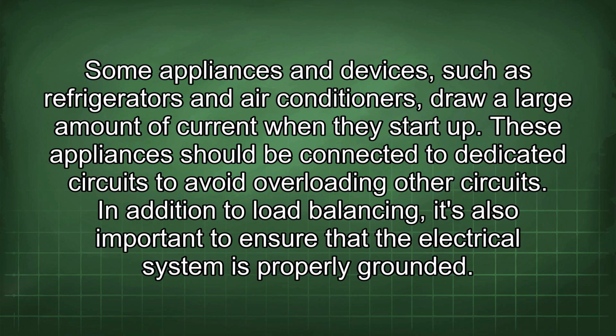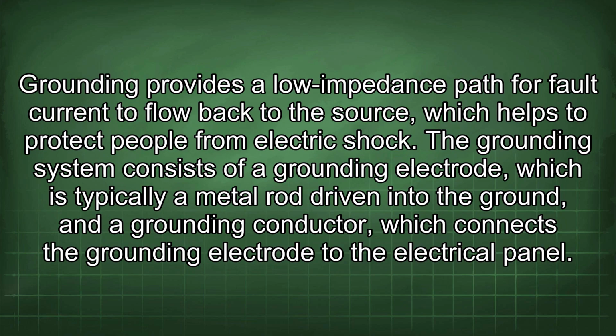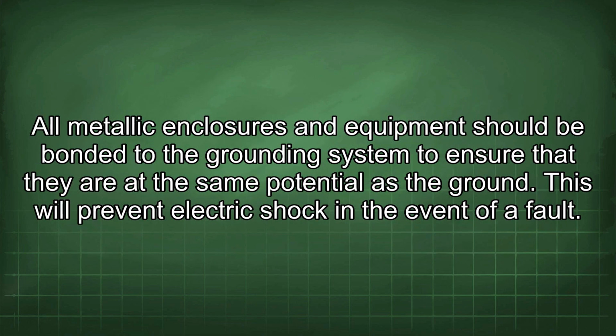In addition to load balancing, it's also important to ensure that the electrical system is properly grounded. Grounding provides a lower impedance path for fault current to flow back to the source, which helps to protect people from electric shock. The grounding system consists of a grounding electrode, which is typically a metal rod driven into the ground, and a grounding conductor, which connects the grounding electrode to the electrical panel. All metallic enclosures and equipment should be bonded to the grounding system to ensure that they are at the same potential as the ground. This will prevent electric shock in the event of a fault.